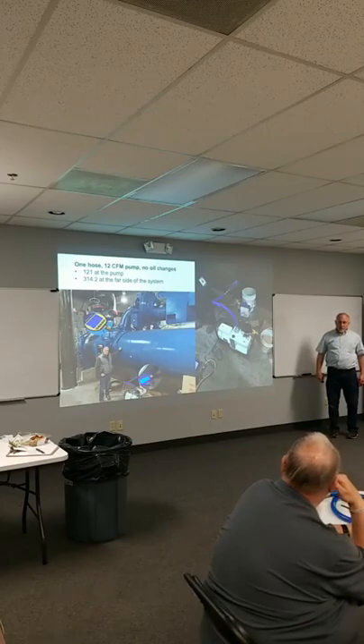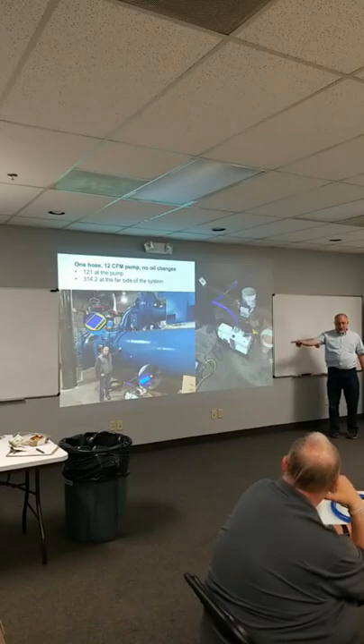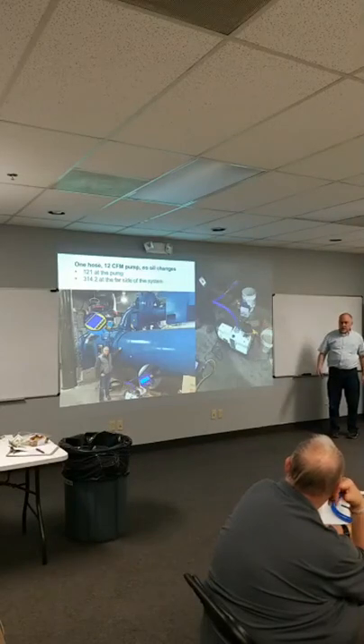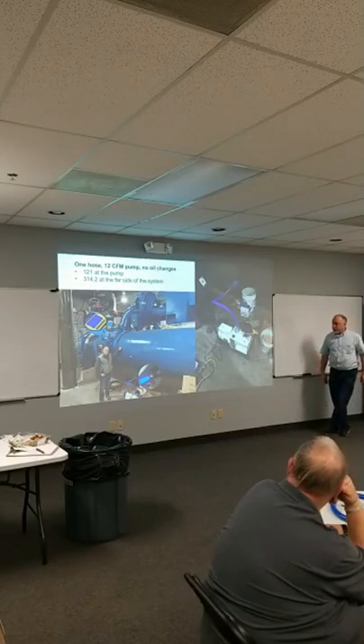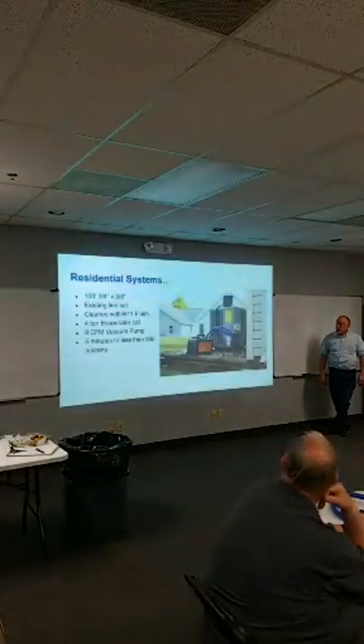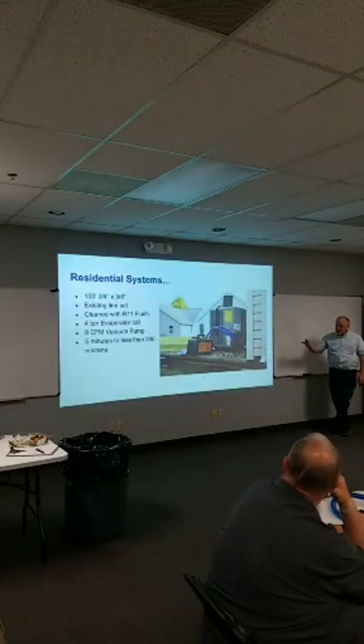So 17 hours. Now we probably could have evacuated that chiller to get down to these levels, we were probably done in 5 hours and didn't realize it, right? So imagine doing a 2,500 ton chiller in 5 or 6 hours. And that's what we did with this 17, because we did it overnight, came back the next day because we're thinking, oh, there's no way it's gonna come down that fast. Well, it did. Right, residential systems, this was that one, 5 minutes down below 200 microns.